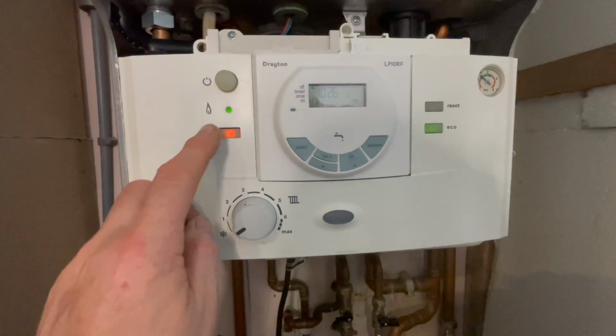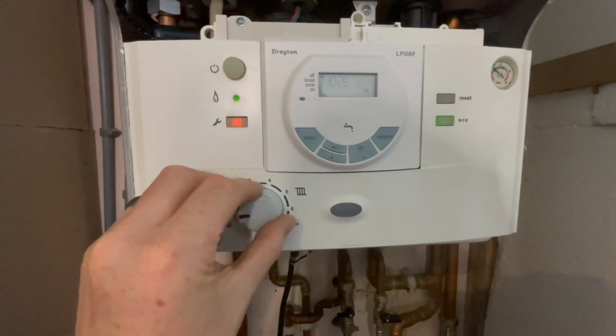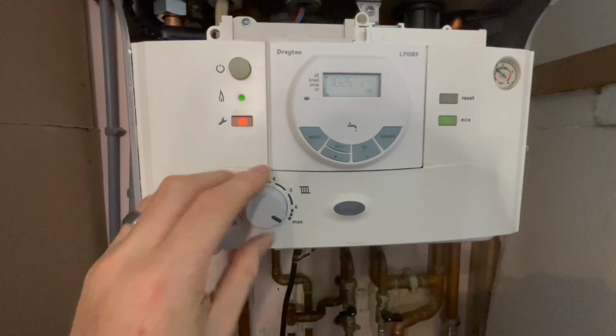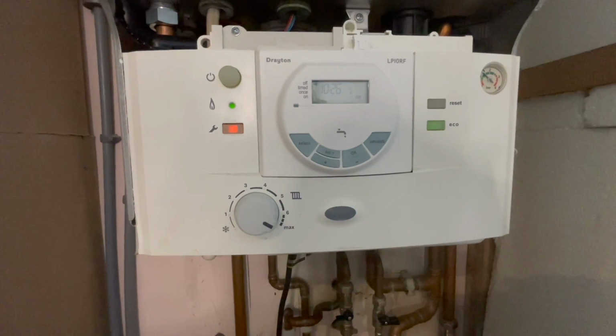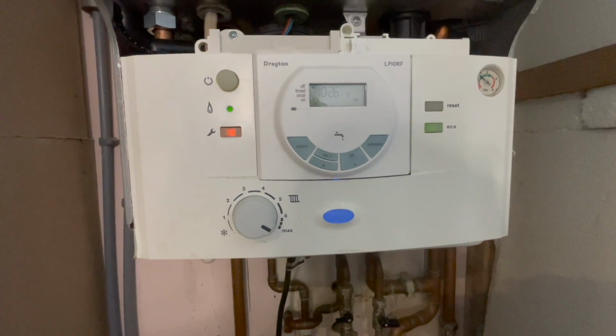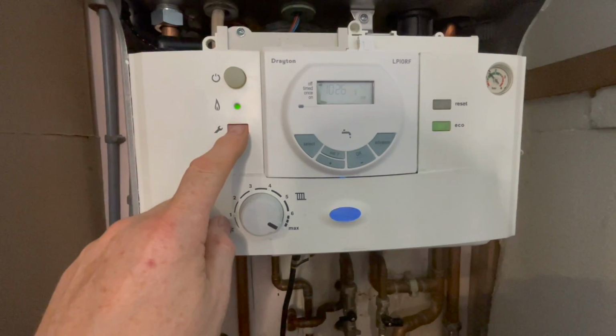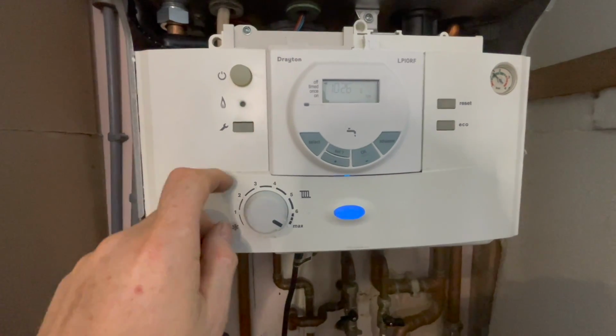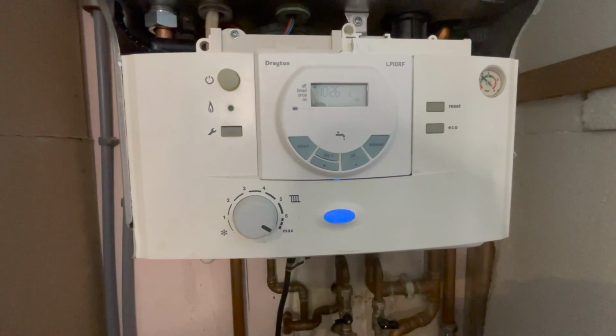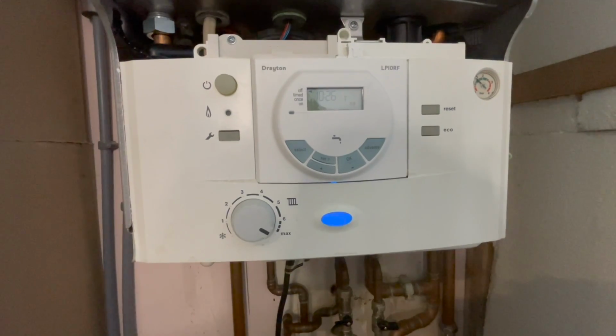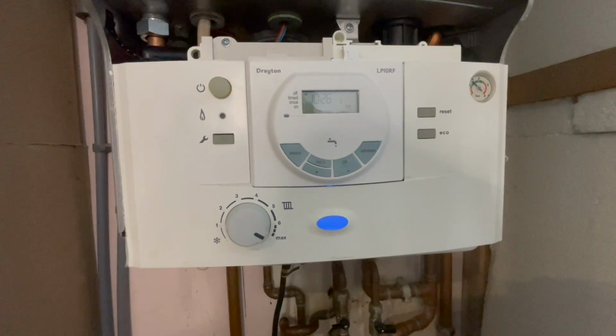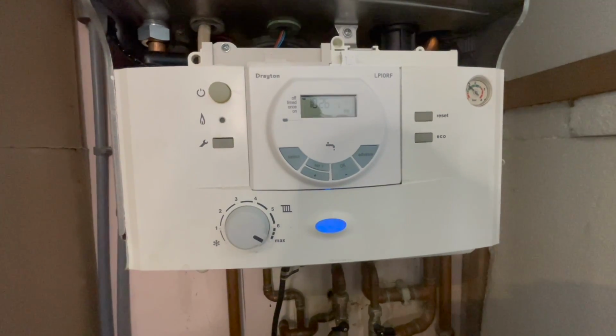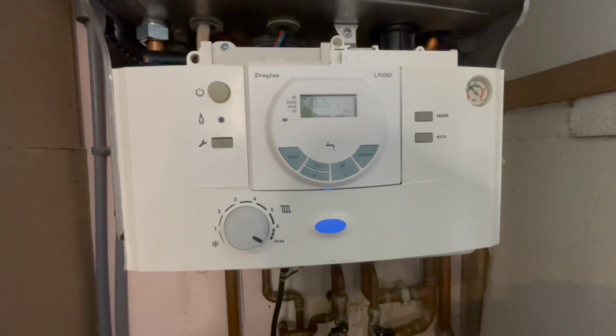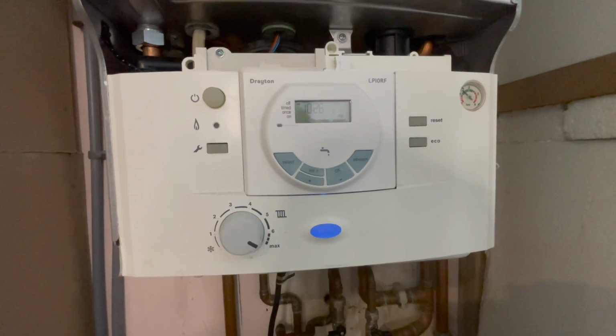There it goes, you can still see the burners lit, and if you turn it all the way around to here, that will now go into maximum rate. And then to come out of the setting, just press the button and it'll go back to normal. So that's how you set a Worcester 28i Junior natural gas or LPG boiler into maximum and minimum settings.